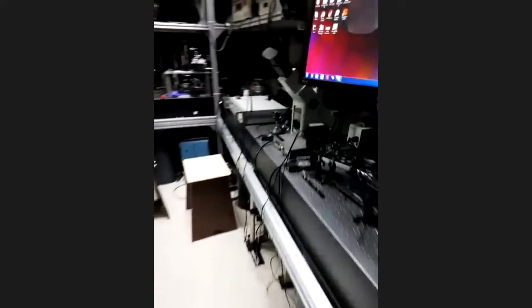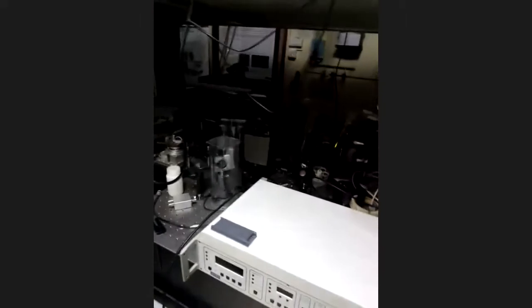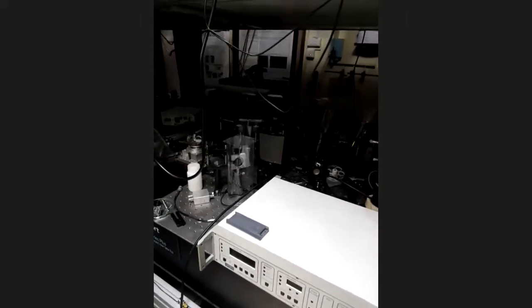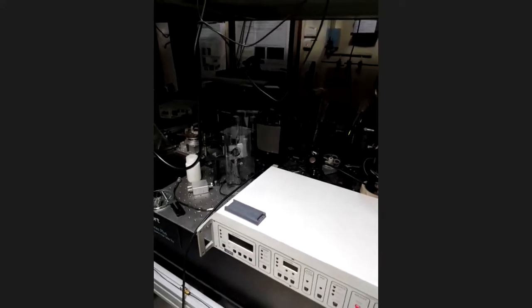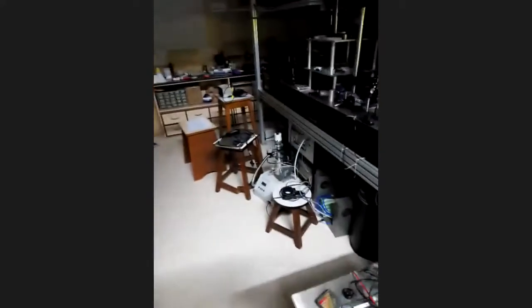Fluctuation in the temperature of the sample. So we use cryostat to maintain the temperature. Other thing, when I showed you this beam splitter, this is a 5-micron thin film. See, if you have an air-conditioned room, the air currents will vibrate that 5-micron film. So that also causes disturbance in the signal which you'll be getting. Okay, so you need to take care of these things so that your air currents are uniform in your lab and inside.